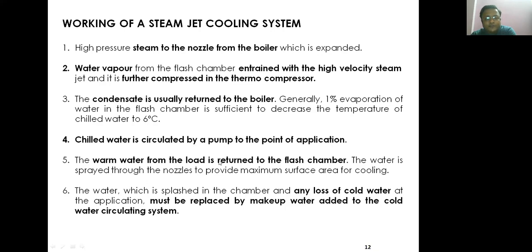The warm water from the load is returned to the flash chamber. The water is sprayed through the nozzle to provide maximum surface area for cooling. The water which is splashed in the chamber and any loss of cold water at the application must be replaced by makeup water added to the cold water circulating system. This is the fundamental procedure of the steam jet cooling system.